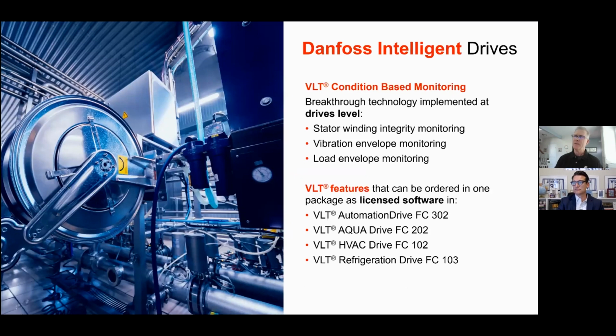The VLT condition-based monitoring is embedded inside the Danfoss Intelligent Drives. Those would be the automation drive series that you see below: the FC302, 202, 102, and the 103. The breakthrough technology is implemented on the levels of the stator winding integrity, the vibration envelope, and the load envelope. Those three are the monitoring points we will use.